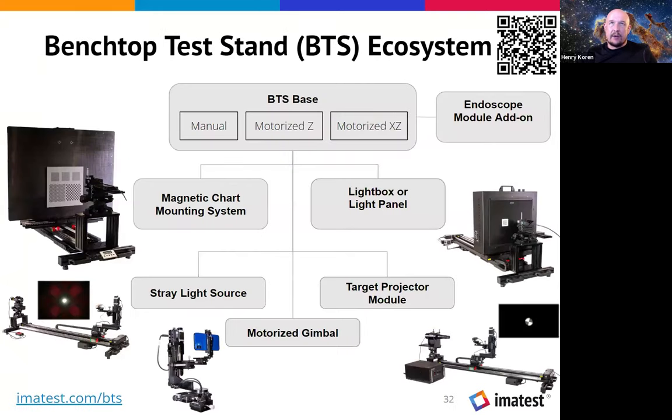So the benchtop test stand, or BTS, I mentioned previously, originally started as an endoscope test system. So we set up a magnetic chart mounting system that attaches, your chart can go right on that board and you can adjust it there or have multiple charts. There's also an endoscope holder included as part of it. The base is manual, and there's a motorized version as well, with the Z stage for doing depth of field tests. And the X stage is usually for switching targets.